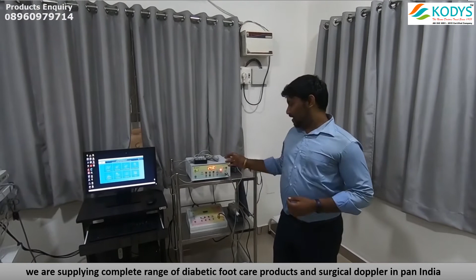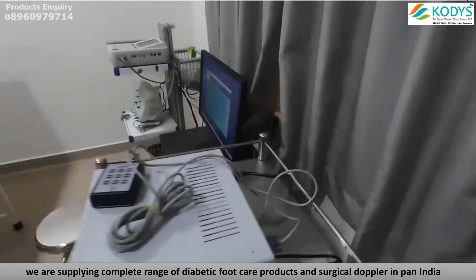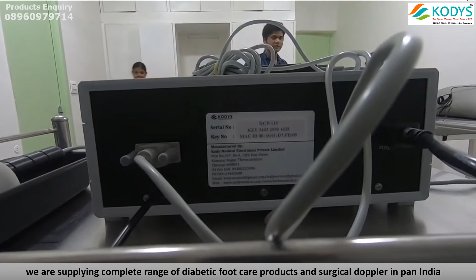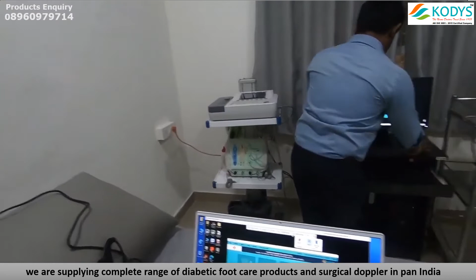The third thing is configuring the device. So we have an option of this key, 12-digit key, that will be printed at the back of the device. So you have to note down these particular values and enter into the system. So we will be seeing this code is aligned HCP testing, and we are going to configure this device. On clicking this, now we have to select this, the code is HCP aligned. Enter the patient information. So we are using demo. Clicking next, we will open the test screen.